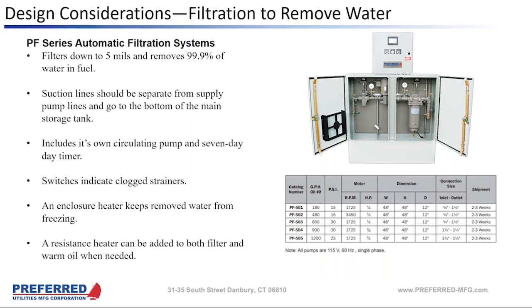David, we get two questions, I think, most frequently when we're talking about polishing. And I do like to use the term polisher rather than filter, just because we're talking about water removal too, right? We're not just talking about particulate. But one of the questions we get is, hey, can I get a pump set filtration set? And like you mentioned there, this really should be on a separate recirculation line if at all possible. We don't want to be sending slugs of water up to a day tank. And we don't really want the filter plugging up to be able to stop us from running our generators.